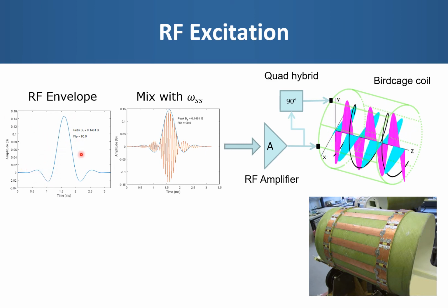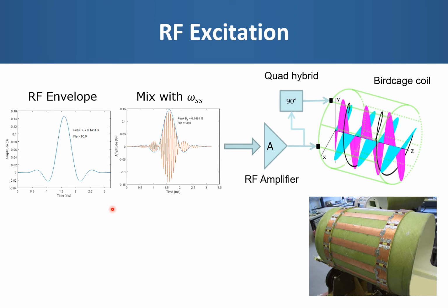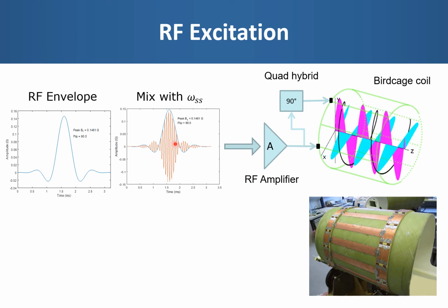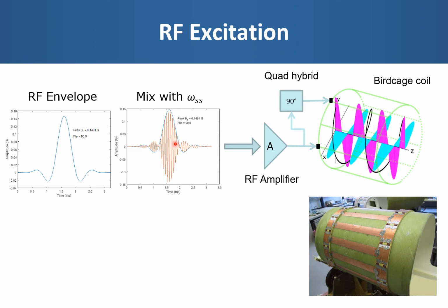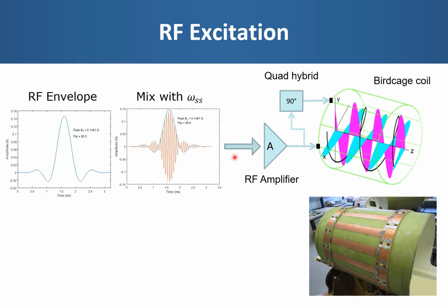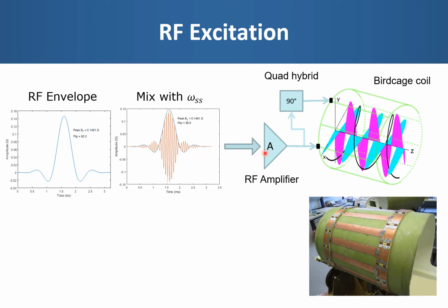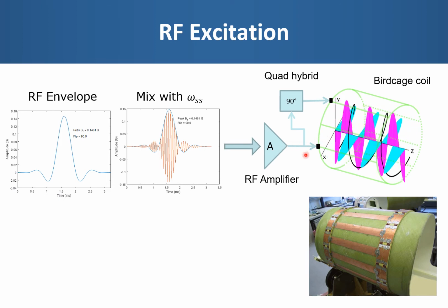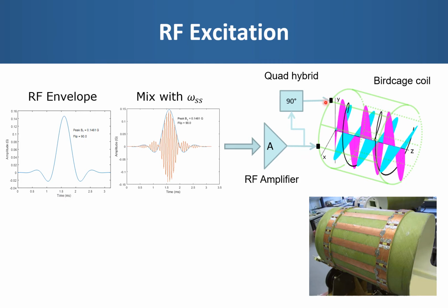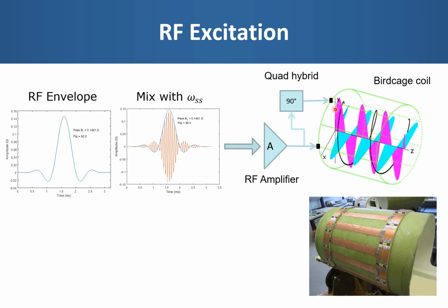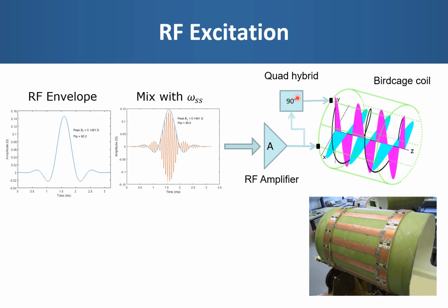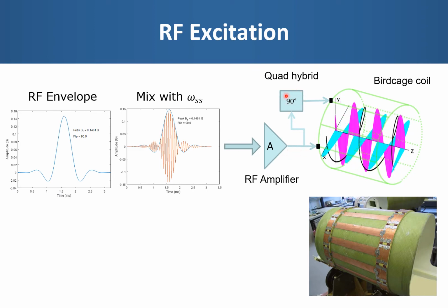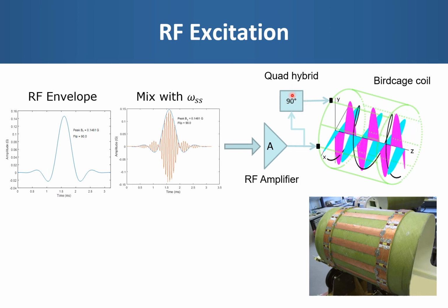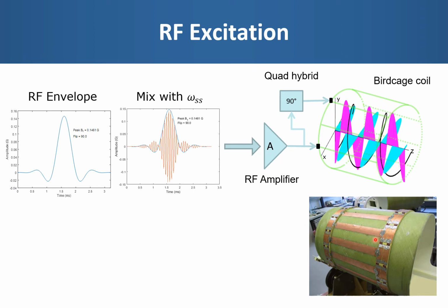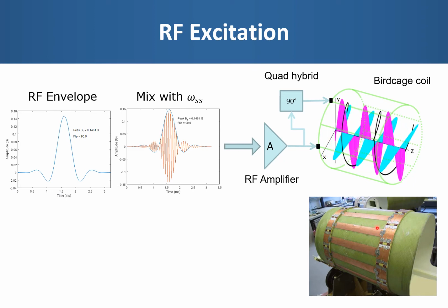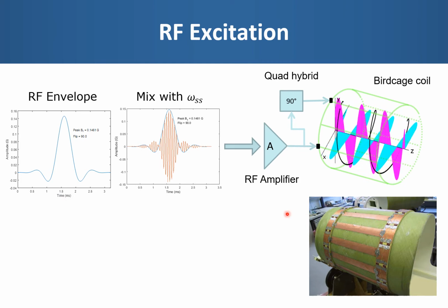As we've discussed before, the RF envelope dictates the bandwidth of the associated slice thickness. This envelope is then mixed with the Larmor frequency for the desired slice offset. This pulse is then applied to the input of the RF amplifier, and in order to create a circularly polarized B1 field, the output of the amplifier drives the birdcage coil at 2 points, 90 degrees physically apart, and with a 90-degree phase shift of the waveform performed using this quad hybrid electronic component. This picture shows a typical 16-rung birdcage body coil that is positioned inside the gradient coil assembly.